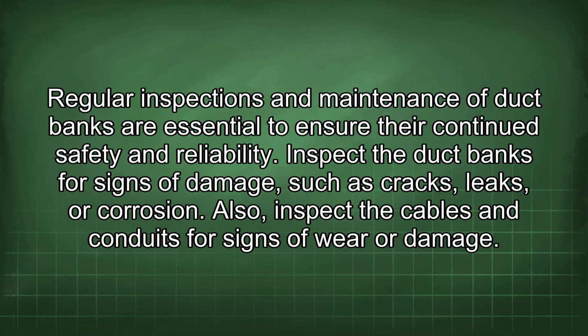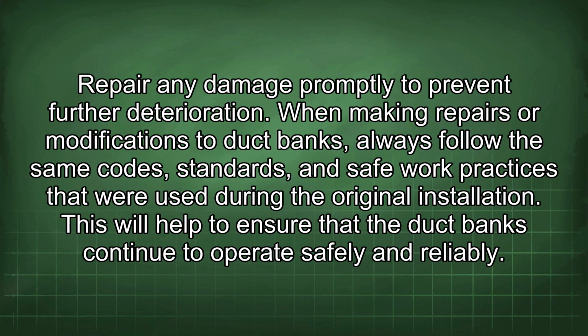Regular inspections and maintenance of duct banks are essential to ensure their continued safety and reliability. Inspect the duct banks for signs of damage such as cracks, leaks, or corrosion. Also, inspect the cables and conduits for signs of wear or damage. Repair any damage promptly to prevent further deterioration. When making repairs or modifications to duct banks, always follow the same codes, standards, and safe work practices that were used during the original installation. This will help to ensure that the duct banks continue to operate safely and reliably.